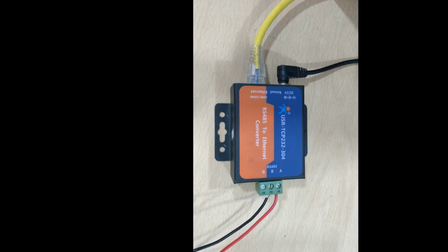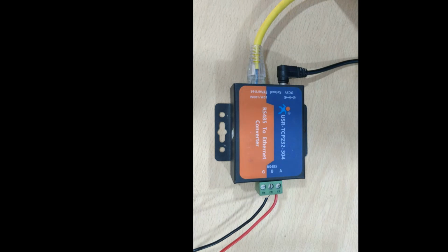This is the setup that you need to get data from the Schneider meter using an RS-485 to Ethernet converter. The wires that you can see here, the red and the black, are the Modbus communication lines that come from your smart meter. This Ethernet is going to the device that acts as the client. In my case, I am using my desktop computer as the client, so the client code will be running on my PC. So this Ethernet wire is connected to my PC.